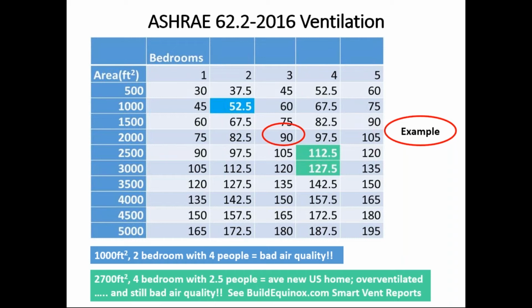There are some problems with this fixed ventilation schedule. At the lower end, 52.5 CFM for a 1,000 square foot two-bedroom home, you put four people in that, and this home is polluted anytime there are people in it. No ifs, ands, buts about it. That's not enough airflow to keep this household healthy. At the other end, the average size US new construction home, about a 2,700 square foot four bedroom home, you're ventilating constantly with 120 CFM. But the average occupancy is only 2.5 people, and so it's over ventilated.